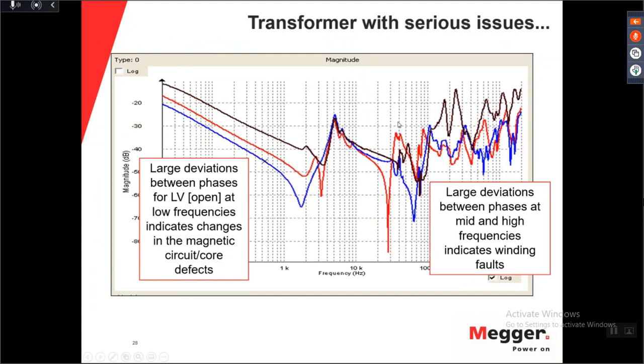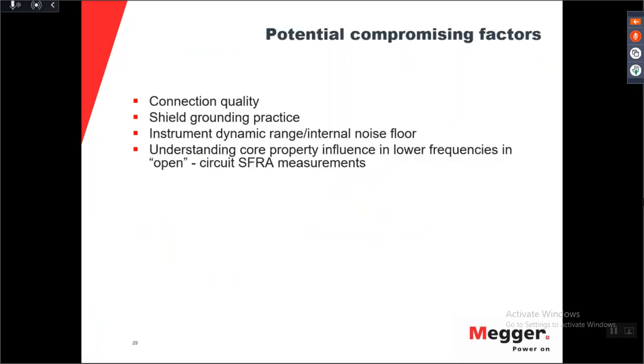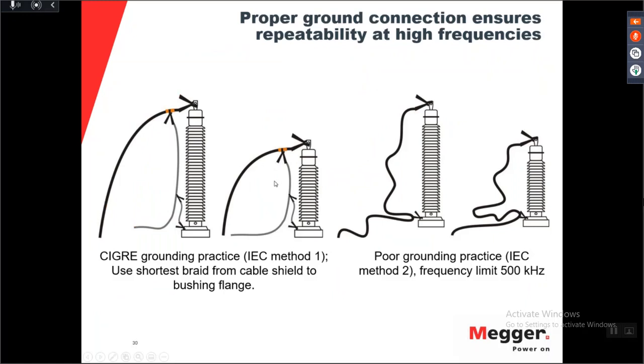As you hear, I say SFRA equipment. You have two different methods, the impulse and the sweep frequency. As of today, all the major manufacturers are using sweep frequency, and the impulse-based method is going further and further away. So when we look at the two top ones, connection quality and shield grounding practice, you can see it here. The connection quality means you should have a tight connection, a good connection.